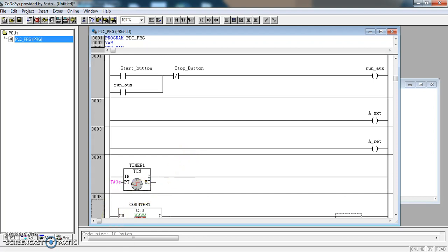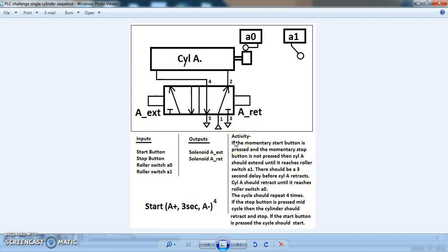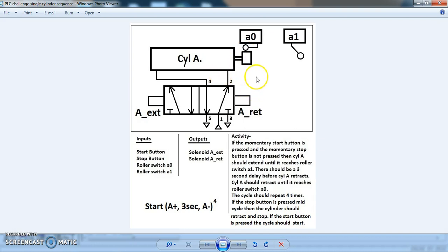Now let's have a look at our task again. The task says if the momentary start button is pressed and the momentary stop button is not pressed, then cylinder A should extend until it reaches roller switch A1. So in the start position A0 is active at that roller switch, and the start button needs to be pressed. Once those two things happen, the Aextend solenoid should come on to make cylinder A extend out.